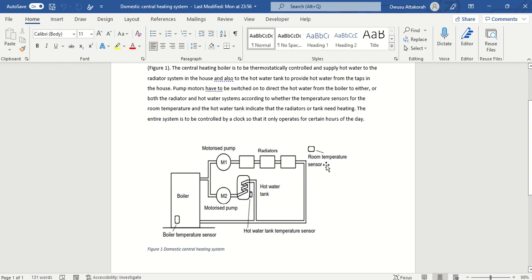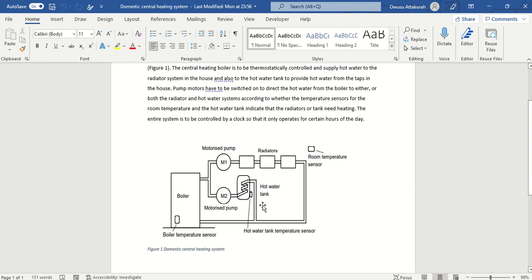For motor M1 to operate, we need the room temperature sensor and the boiler sensor to draw water through the radiators. For motor M2, we also need the boiler temperature sensor and the hot water tank temperature sensor to allow M2 to circulate water through the water tank to raise the temperature of the water supplied to taps in the house.